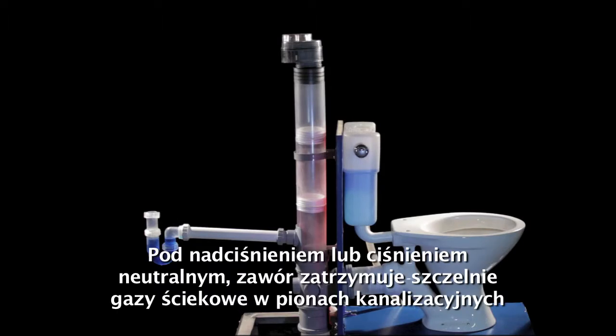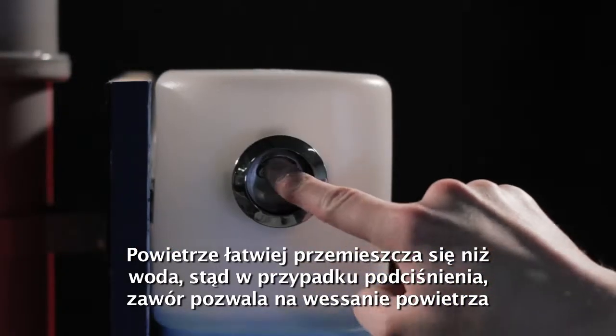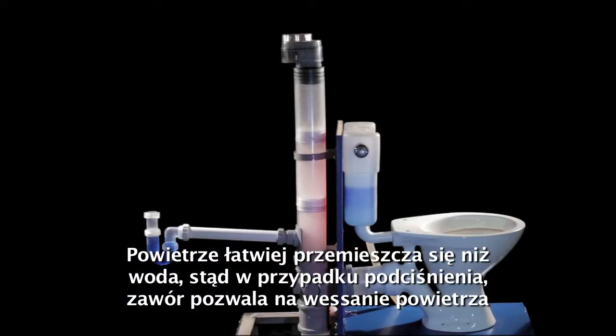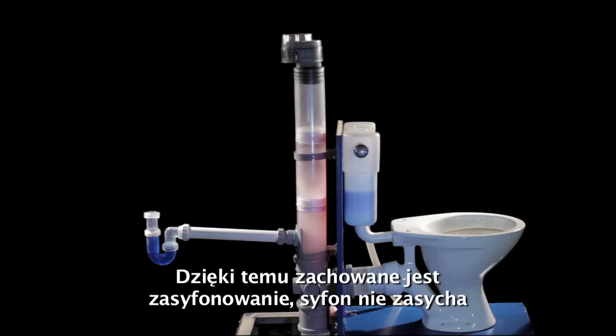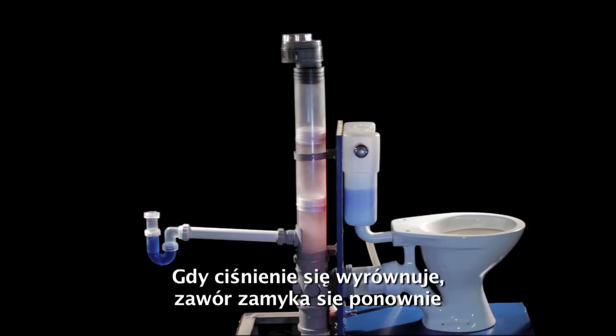Under positive or neutral pressures, it remains airtight, keeping sewer gas within the system. It is much easier to move air than water, so during negative pressure, it allows air to be drawn in. This ensures water seals are maintained. When the pressures equalise, the valve closes again.